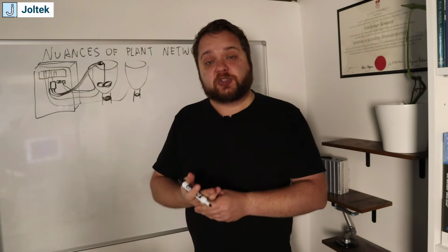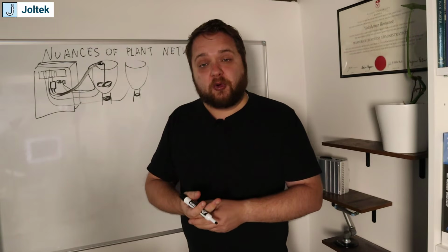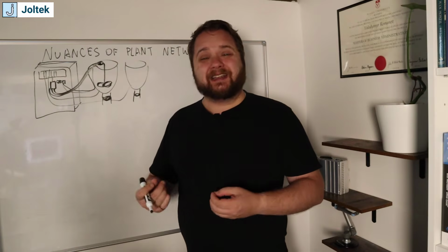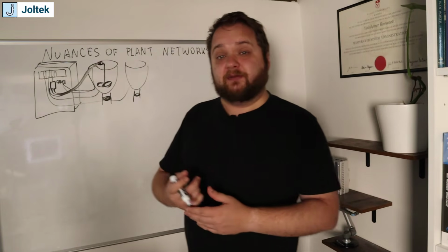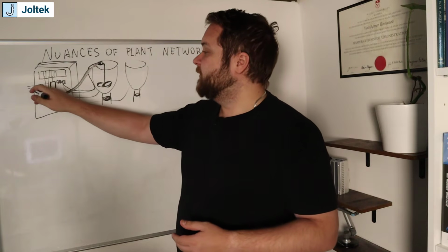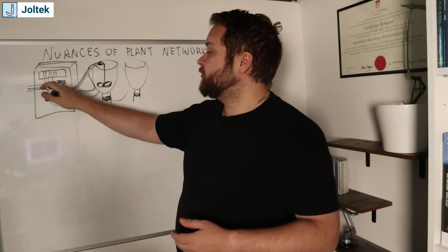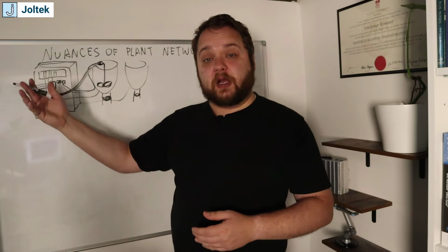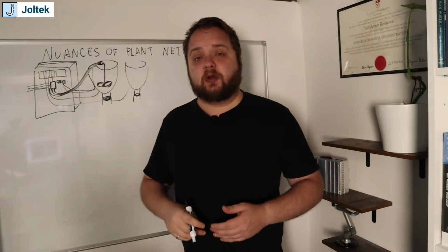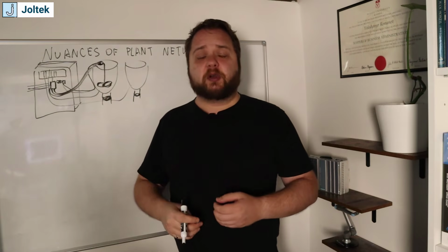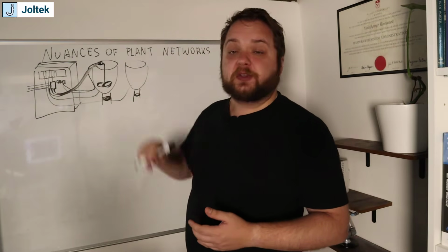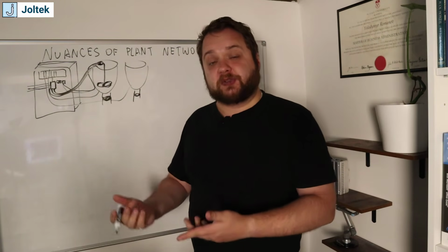I can set the speed, I can perhaps vary the torque, I can maybe change the frequency, which is going to vary the speed. I can set other parameters, I can set maybe voltage, right? So you have 3 phases coming into this VFD, and that is obviously going to be set by the transformer or the upstream system. But in this case, maybe I want to change the motor type. Maybe I want to run at 230, maybe I want to run it at 480, right? So there's going to be different options that you can set via this drive by using the Modbus registers.